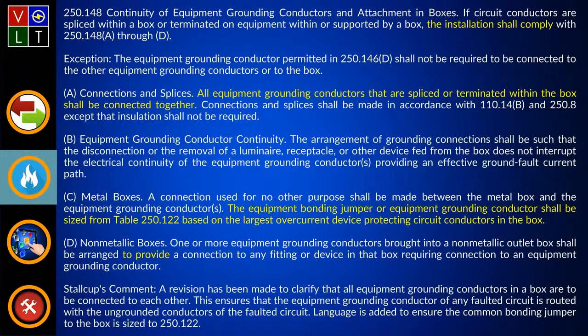And the reason they do this is to ensure that the equipment grounding conductor, where you have any type of faulted circuit, is routed with the ungrounded conductors of the faulted circuit.